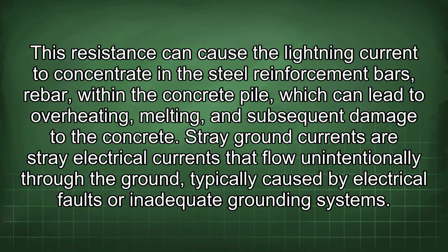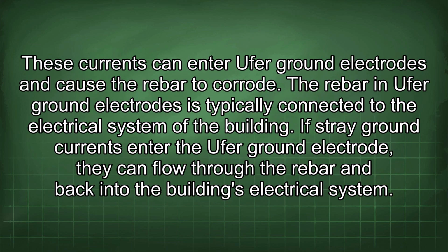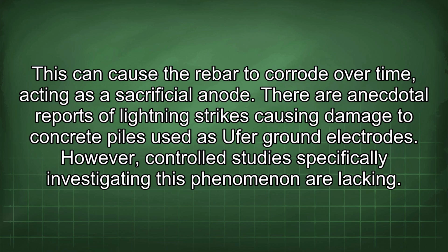Stray ground currents are stray electrical currents that flow unintentionally through the ground, typically caused by electrical faults or inadequate grounding systems. These currents can enter Ufer ground electrodes and cause the rebar to corrode. The rebar in Ufer ground electrodes is typically connected to the electrical system of the building. If stray ground currents enter the Ufer ground electrode, they can flow through the rebar and back into the building's electrical system. This can cause the rebar to corrode over time, acting as a sacrificial anode.